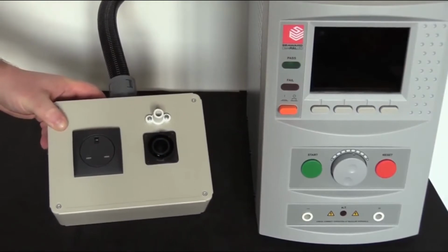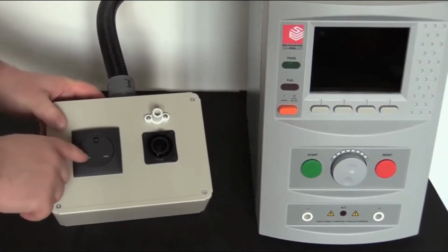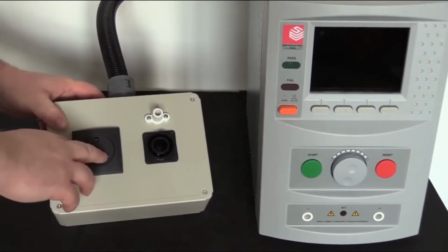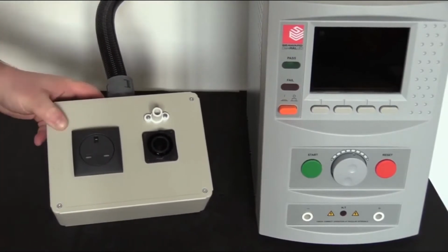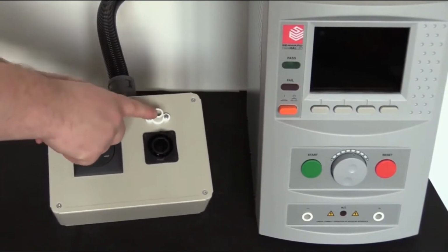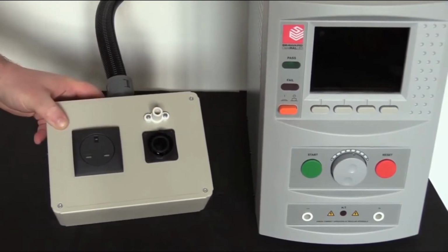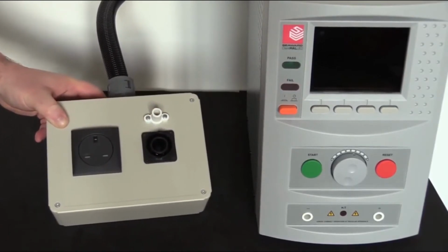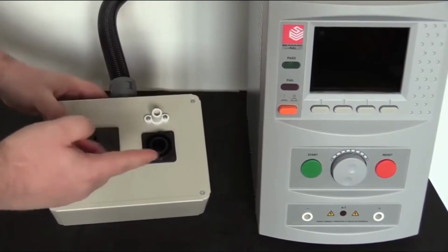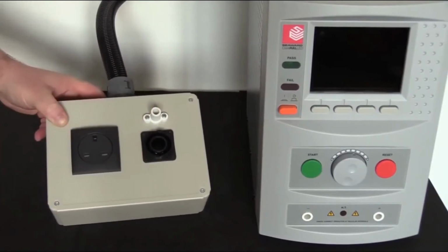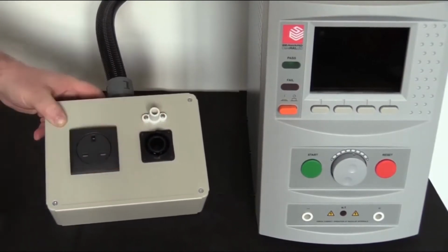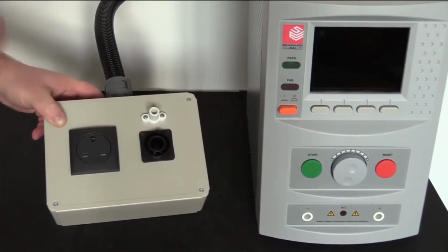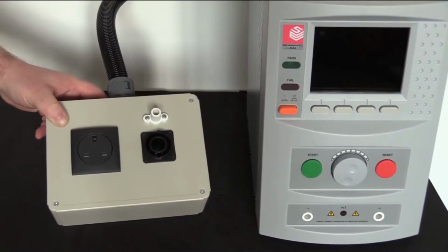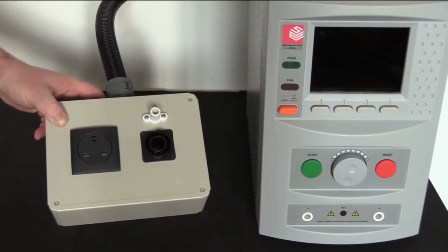If your product is a class 2 that you'll be testing, we would still use our live and neutral strapped together as the output, but in this case we would use our return for measuring any stray current. So in that case we could use either our Hipot clip or the Hipot probe we spoke about before, place those into this connector, and then connect your probe or your clip to any exposed conductive parts on your double insulated product, and we'll measure for any current flow returning back into the instrument.